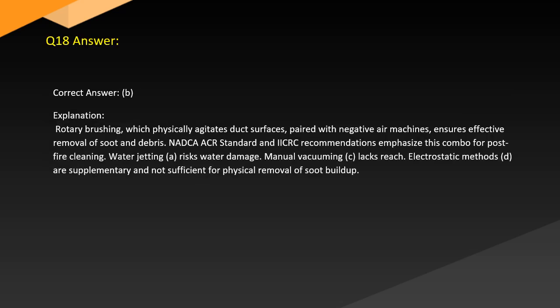Answer. Correct answer: B. Explanation. Rotary brushing, which physically agitates duct surfaces, paired with negative air machines, ensures effective removal of soot and debris. NADCA, ACR Standard and IICRC recommendations emphasize this combo for post-fire cleaning. Water jetting, A, risks water damage. Manual vacuuming, C, lacks reach. Electrostatic methods, D, are supplementary and not sufficient for physical removal of soot buildup.